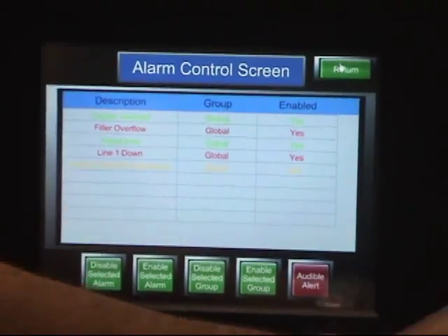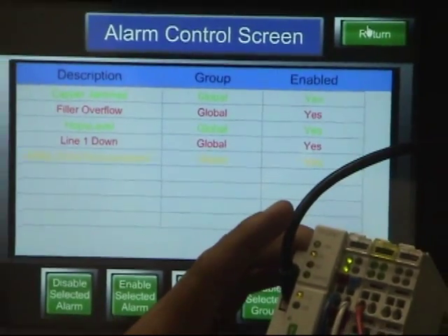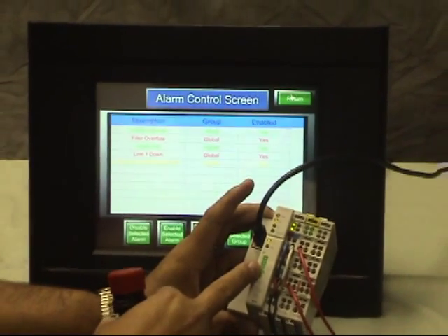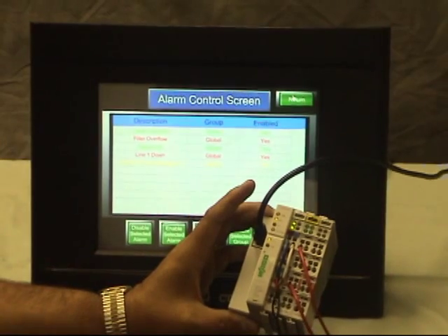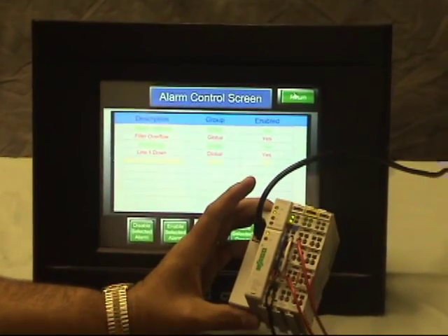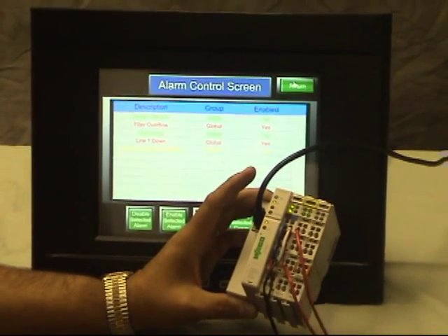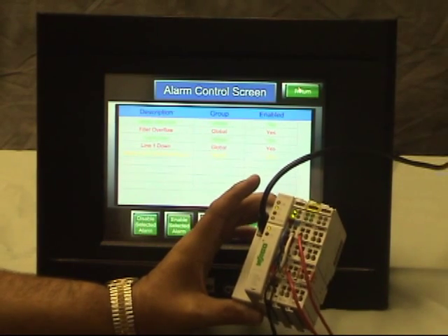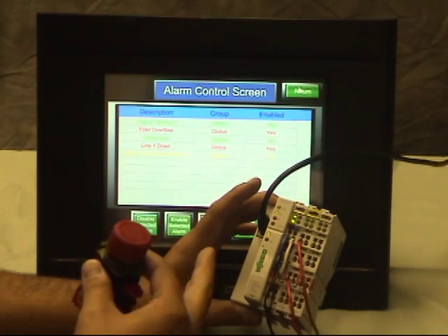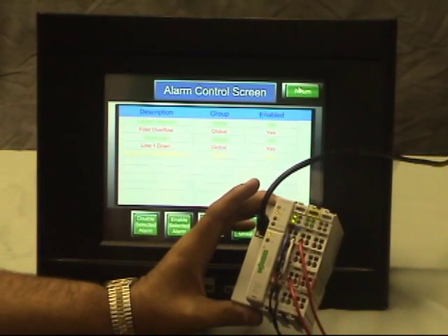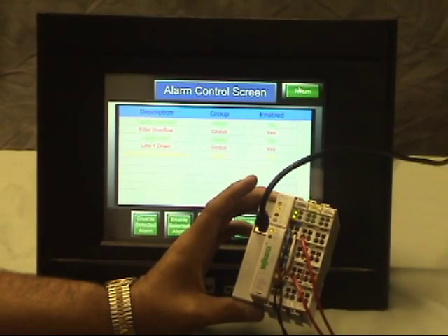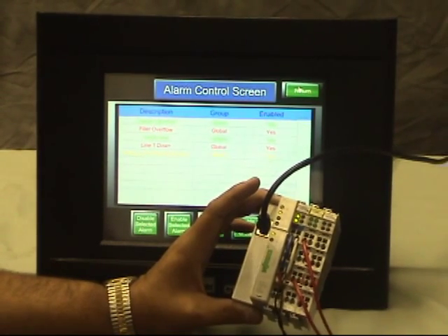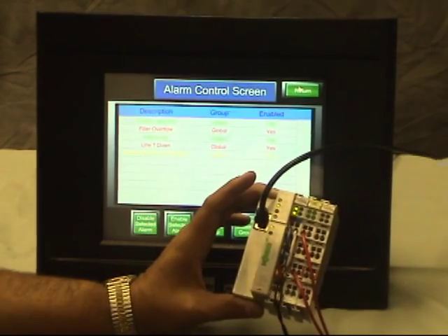Now with our distributed I/O module, what is beautiful about this is it's very modular. In this particular case, I've got an Ethernet bus coupler which allows us to communicate on a plant-wide Ethernet network. I've got a four-channel digital input module so I could read the status of four different segments of a machine, whether or not they're running. And I've got an end module. I can add more modules as I need in order to collect various information about a machine or a production line. Each one of your machines would have one of these located in the main control panel to collect various data about the health of that machine.